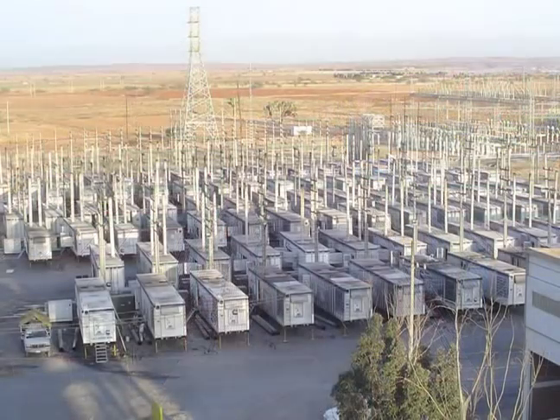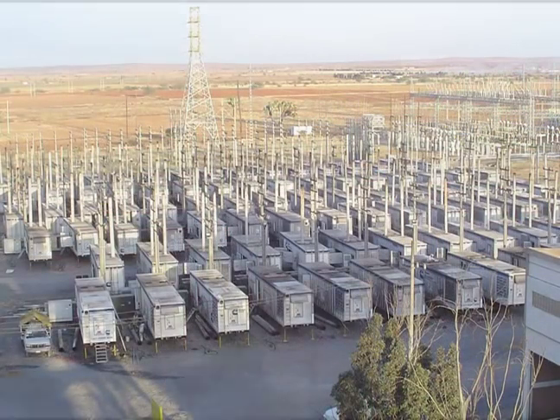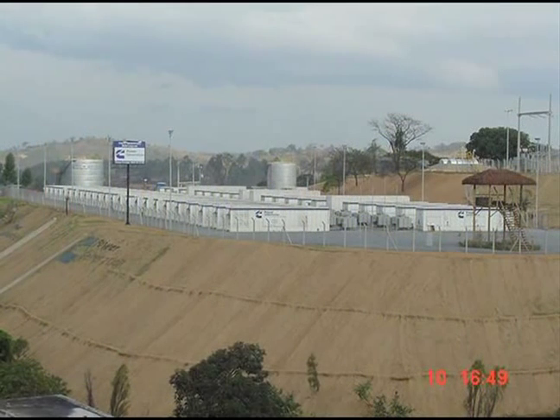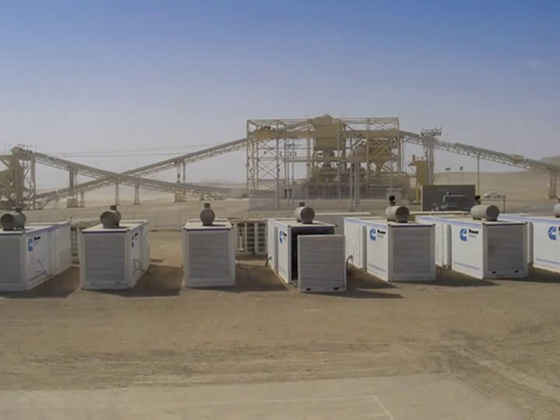In fact, if you have several large generator sets in one location, they can create their own microclimate from the heat they give off. This is important since the higher ambient temperature affects the air intake, which in turn affects the generator performance.